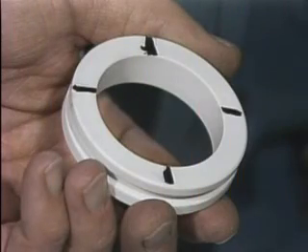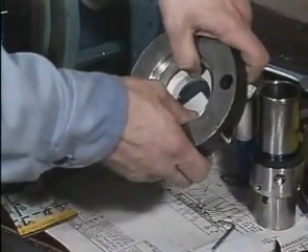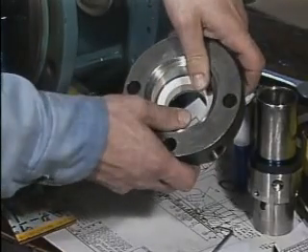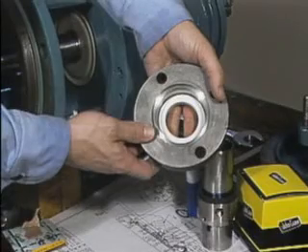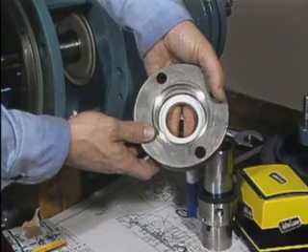The mating ring has a polished side and an unpolished side. Most manufacturers mark the unpolished side of the ring to distinguish it from the polished one. The mating ring is inserted into the gland plate so that the unpolished side goes in first. Inserting the mating ring this way allows the polished side to face toward the rotating seal face when the rotating element is installed.